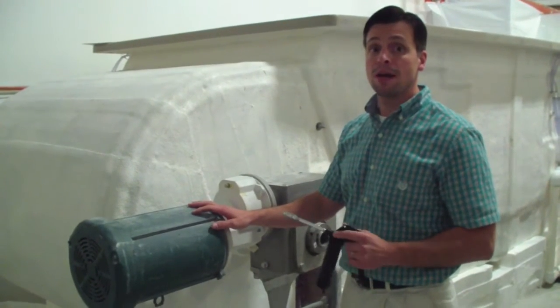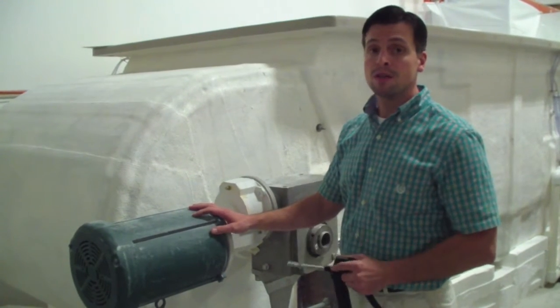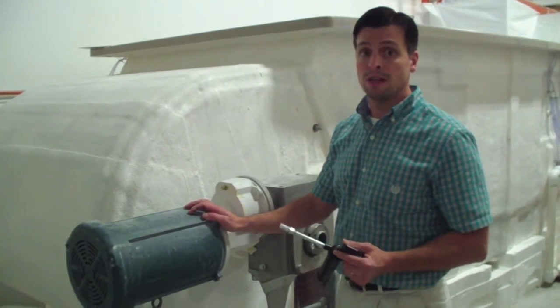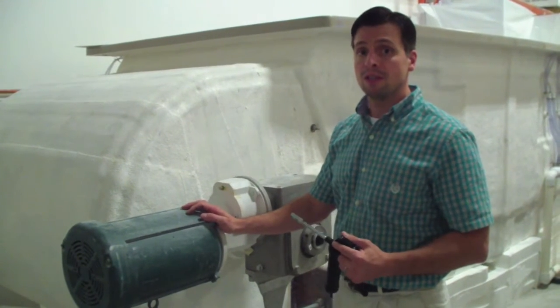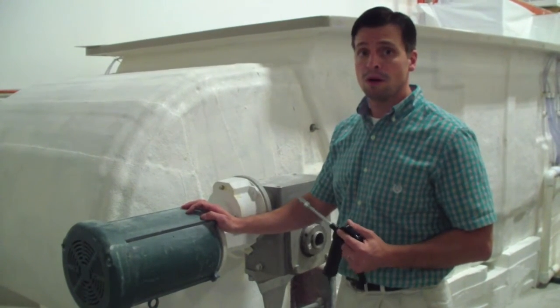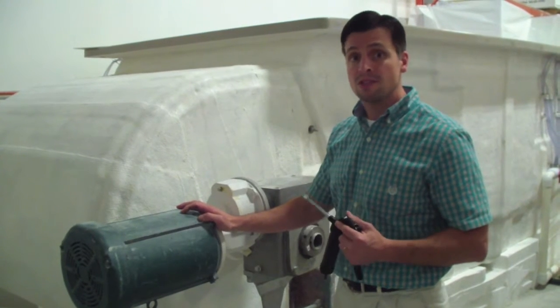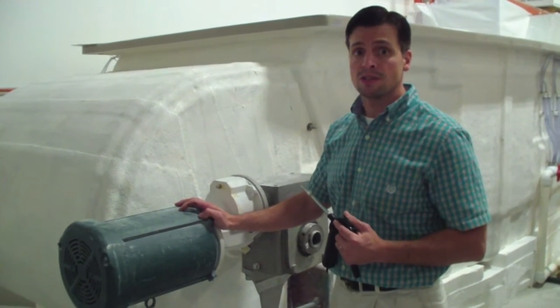Once you've done greasing the paddle wheel bearings, what you want to do is take a look at your gear motor. Some of our gear motors have Zerk fittings on them. Some of them don't. So it's going to take a little inspection. On this particular unit here, we have a 7.5 horsepower motor. And this motor does indeed have two Zerk fittings. So we'll go through greasing this set this time.